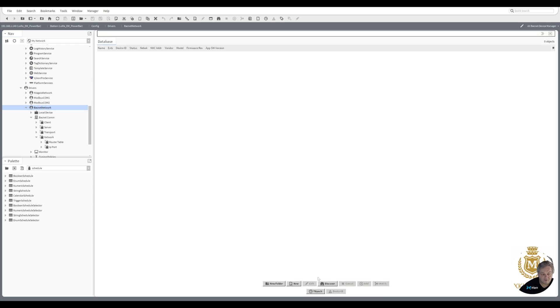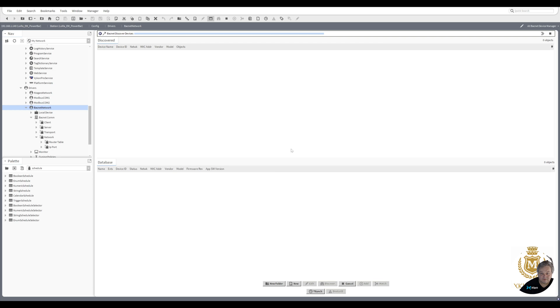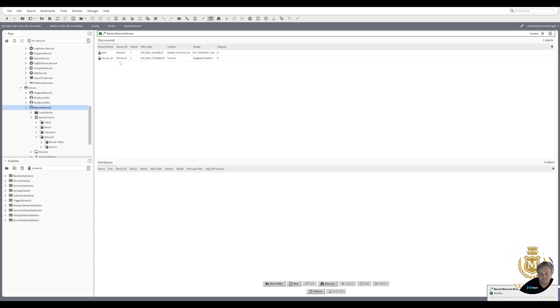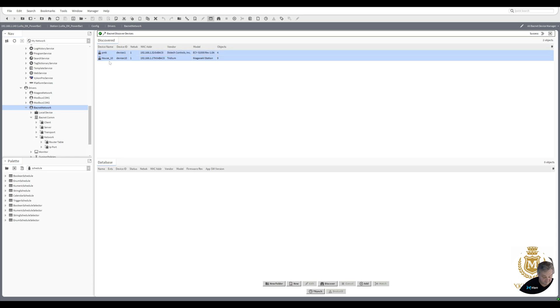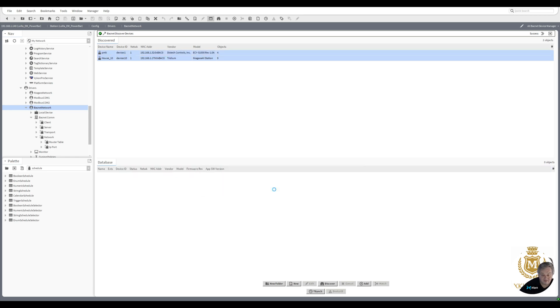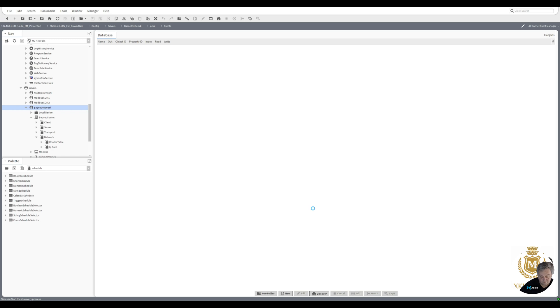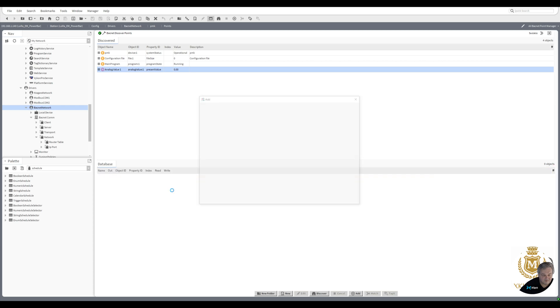If we look at what we've got on the BACnet, we discover. Discover bar's going across the top there. We've got two devices on the BACnet, so I can bring both them devices in just like that. Then I can bring the points in by clicking on one of the devices, discover. That's going to now discover all the points if there is any, which there's just one analog value, and I can drag that in.